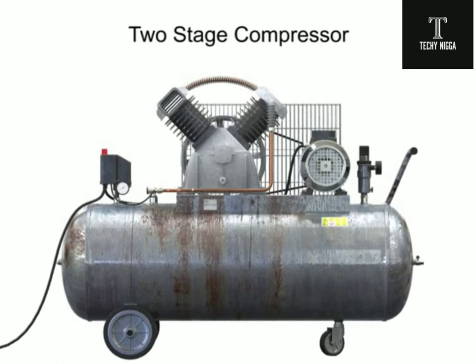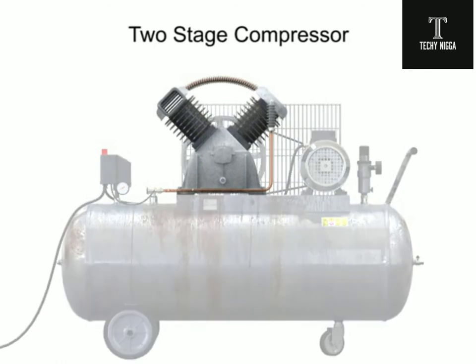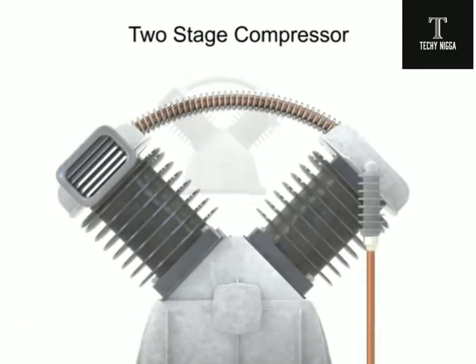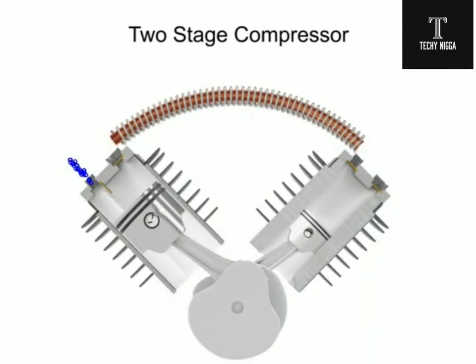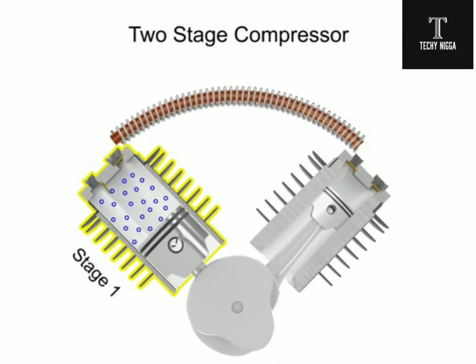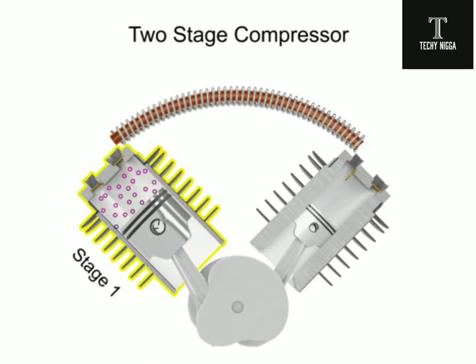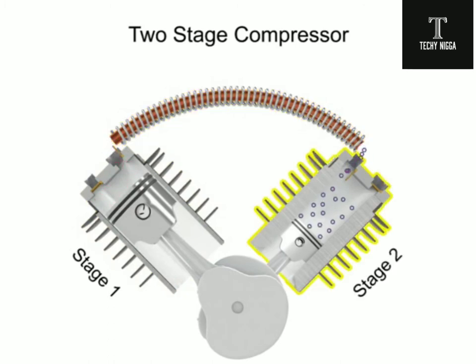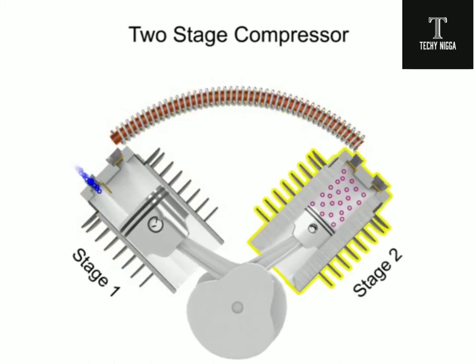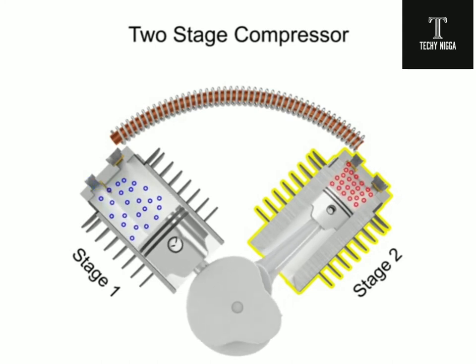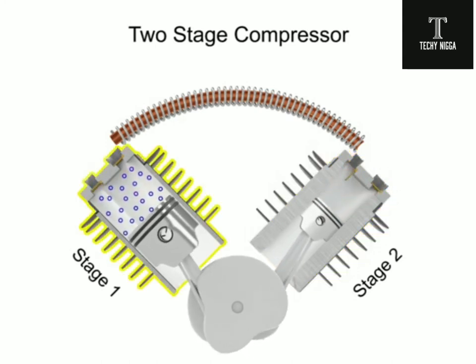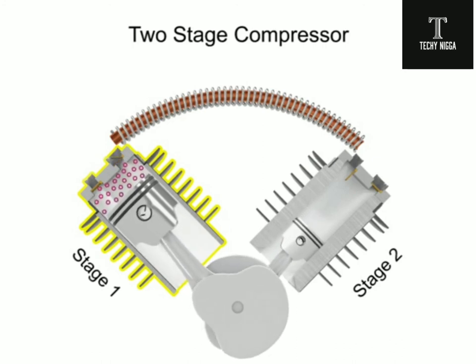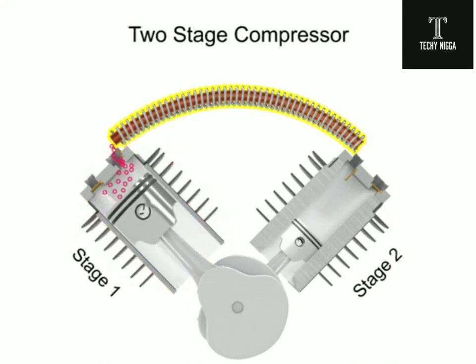To avoid the hazards of overheating and still generate higher pressures, manufacturers make compressors with multiple stages. The air is compressed in the first stage, which is typically the largest stage, then cooled, then compressed in a second stage. The hot compressed air from the first stage is conducted to the second stage through finned tubing, which is exposed to the air from a flywheel fan.